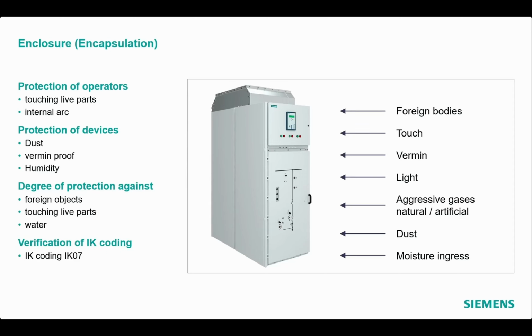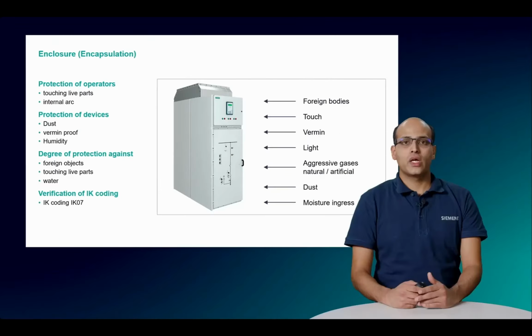The degree of protection, in other words, ingress protection, in short, the IP rating as defined by standards, indicates the degree to which an enclosure safeguards against the ingress of solid foreign objects and water. The enclosure provides a certain degree of protection against the mechanical impacts, which is defined by an IK coding.